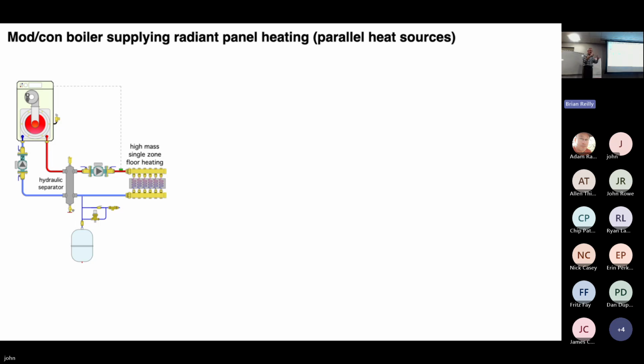I mean, if there was ever a hydronics museum, the Taco 007 should be in that museum. It is the most ubiquitous circulator. There's millions of them out there. But the wire to water efficiency on that circulator is probably between 15 and 20%. And that is not just because it's a Taco circulator. The wire to water efficiency of a Grundfos equivalent would be right about the same spot. They aren't very efficient at converting electricity into kinetic mechanical energy to push fluid through a circuit.